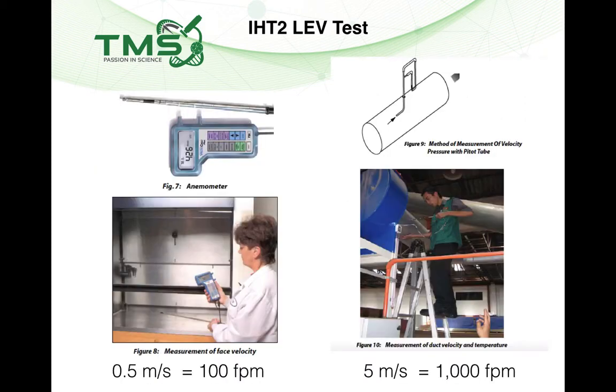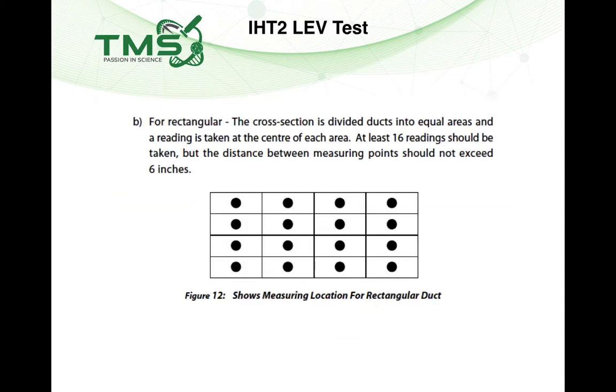These are the typical tests run by Hygiene Technician 2. The first is to measure the face velocity at the opening of the fume hood. The required face velocity is 0.5 meters per second, or 100 feet per minute. Hygiene Tech 2 will also measure the velocity pressure and total pressure within the duct lines; the typical required velocity in the duct line is 5 meters per second, or 1,000 feet per minute. When measuring face velocity, they collect at least 16 to 25 data points, with measurement points no more than 6 inches apart — one measurement every 6 inches.